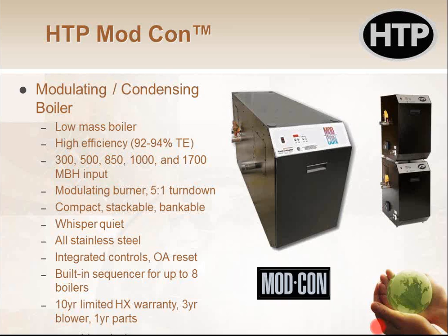So you can get 1.7 million BTUs, one boiler, but internally it's really 2 boilers stacked together. It's got some redundancy there. Same exact heat exchanger, same exact controls. It's low mass. You still do the primary, secondary. Because it is a commercial product, you'll see the warranty down there. It says it's a 10-year warranty instead of 12. For whatever reason, that's pretty common with the boiler manufacturers, but it's still 3-year blower and 1 year on the parts. So that's the big guy there.